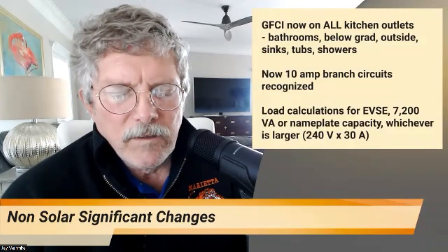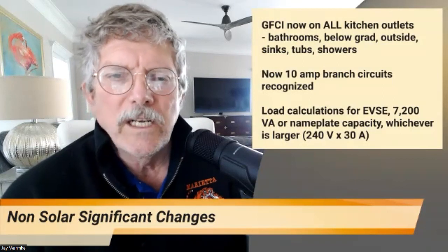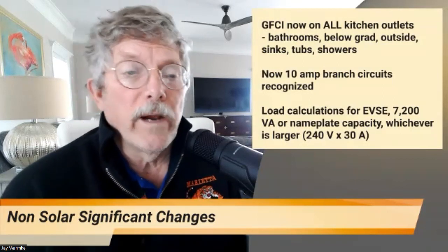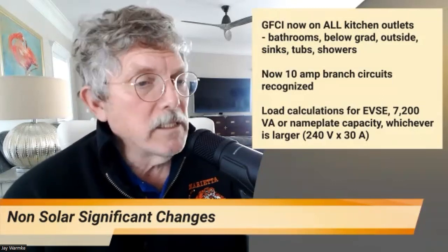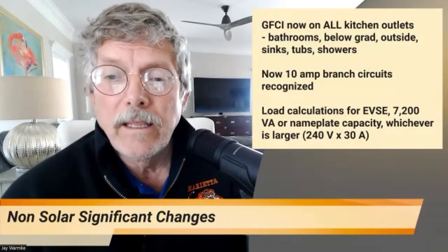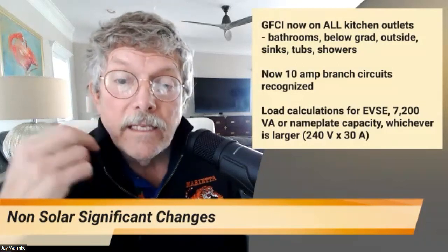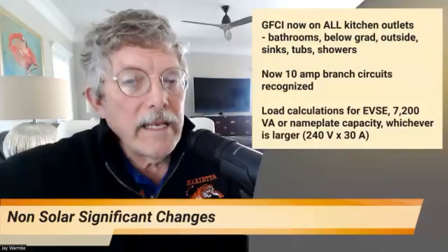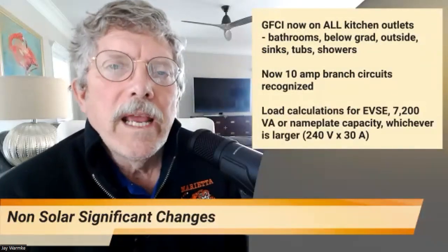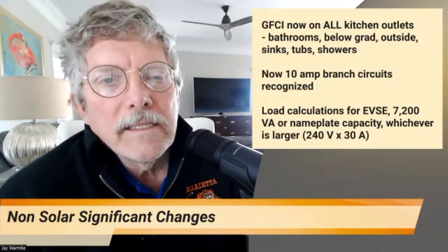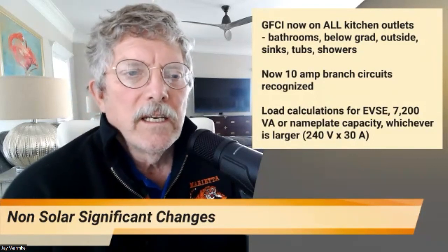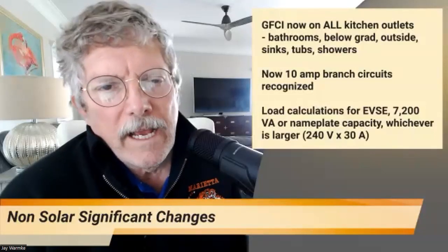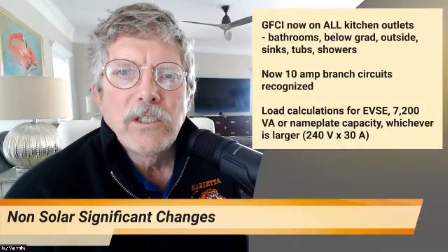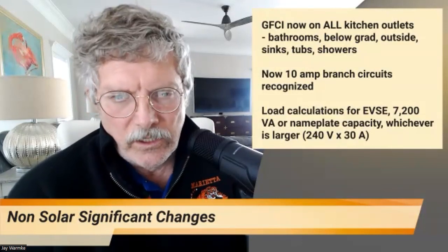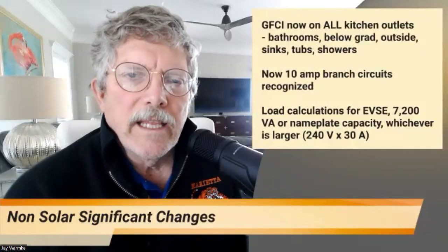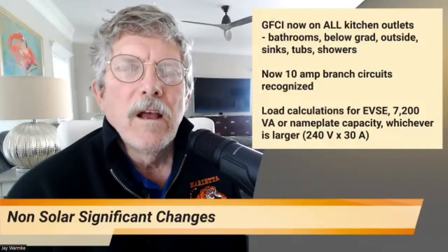All of the bathroom outlets have to be GFCI. All of the kitchen outlets have to be GFCI. Any part of the home that's below grade, so a basement, has to be GFCI. Everything in the basement, anything outside has to be protected. So they're expanding this out quite a bit. They also announced that they will recognize 10 amp branch circuits. I hadn't even realized, apparently before, 15 amp branch circuits were the smallest amperage that the NEC recognized in a traditional service panel.